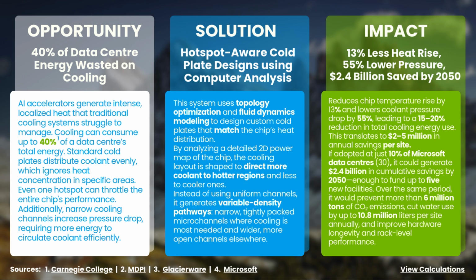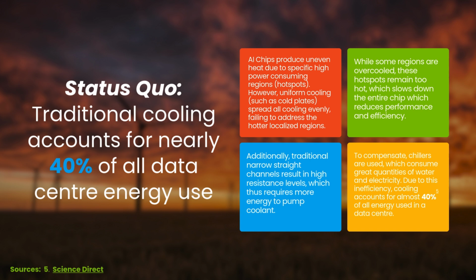AI chips generate intense heat in small areas, but traditional cooling systems don't focus where it's needed. They waste energy and can hurt performance. Our solution is to redesign cold plates so they send coolant right to the hotspots. This means $2 to $5 million in savings per data center every year. If just 10% of Microsoft data centers use this, we'd save $2.4 billion by 2050, cut over 6 million tons of CO2, and save over 10 million liters of water per site annually.